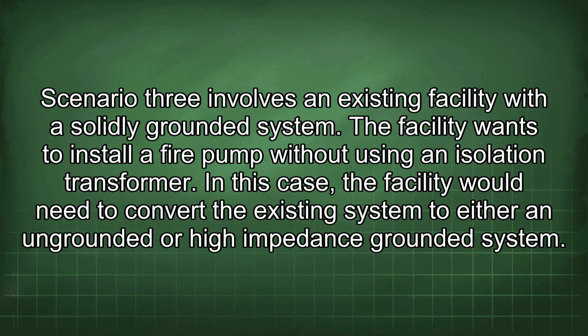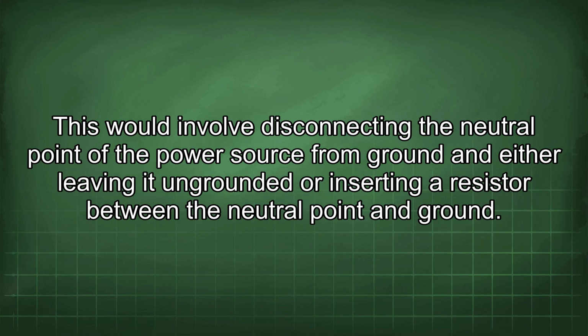Scenario 3 involves an existing facility with a solidly grounded system. The facility wants to install a fire pump without using an isolation transformer. In this case, the facility would need to convert the existing system to either an ungrounded or high impedance grounded system. This would involve disconnecting the neutral point of the power source from ground and either leaving it ungrounded or inserting a resistor between the neutral point and ground.